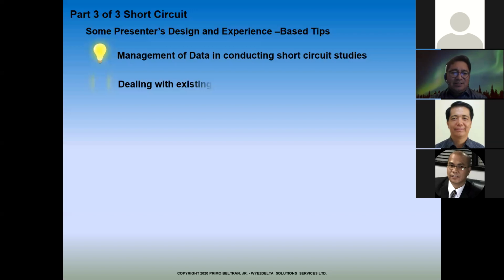Switching and bypassing a reactor is one way. So both are trying to mitigate - one is isolating, and one is permanently connecting and limiting the fault. So I would rather put a fixed reactor there instead of an IS limiter, so I don't need the IS limiter. You cannot have both, because that complicates your system.